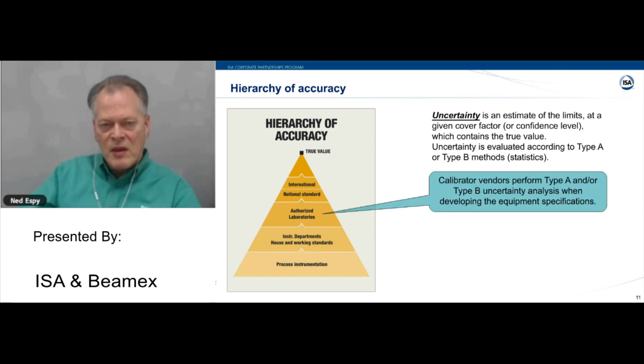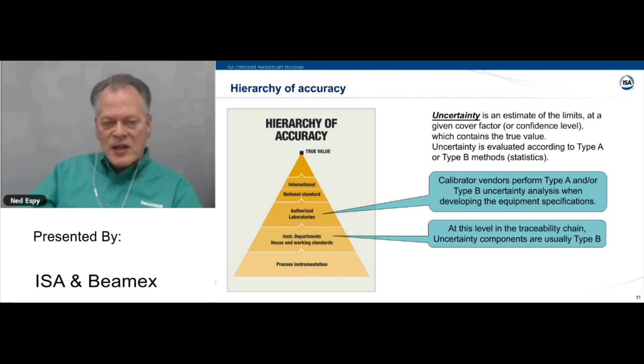But the good news is, when a calibrator vendor analyzes the uncertainty of their instrument, they perform Type A and Type B uncertainty analysis. I'm not going to get into that detail here, but the good news for the process folks is that when you get to the level out on the plant floor, your components almost always fall into the Type B category. So you only have to have one method in analyzing things.